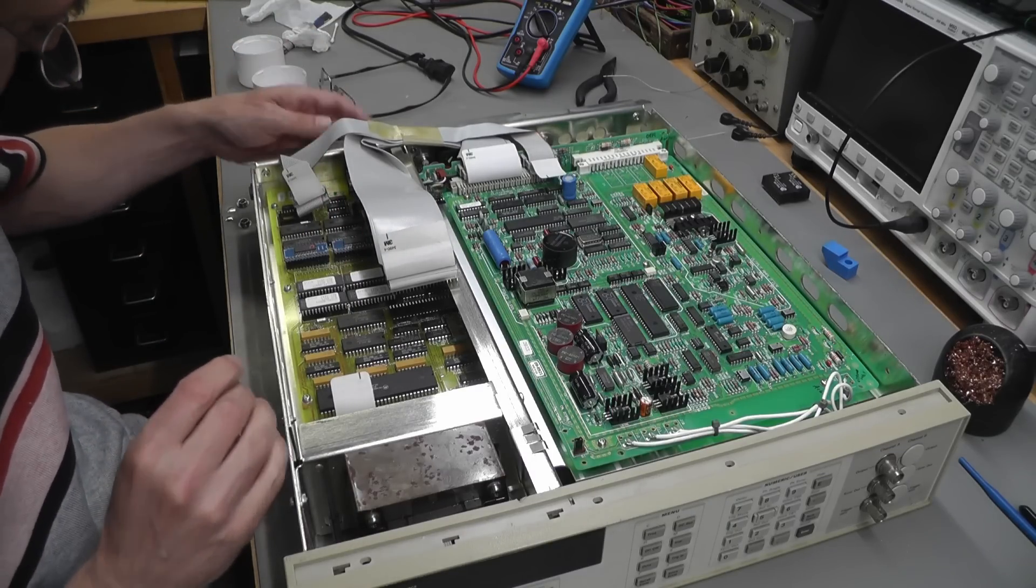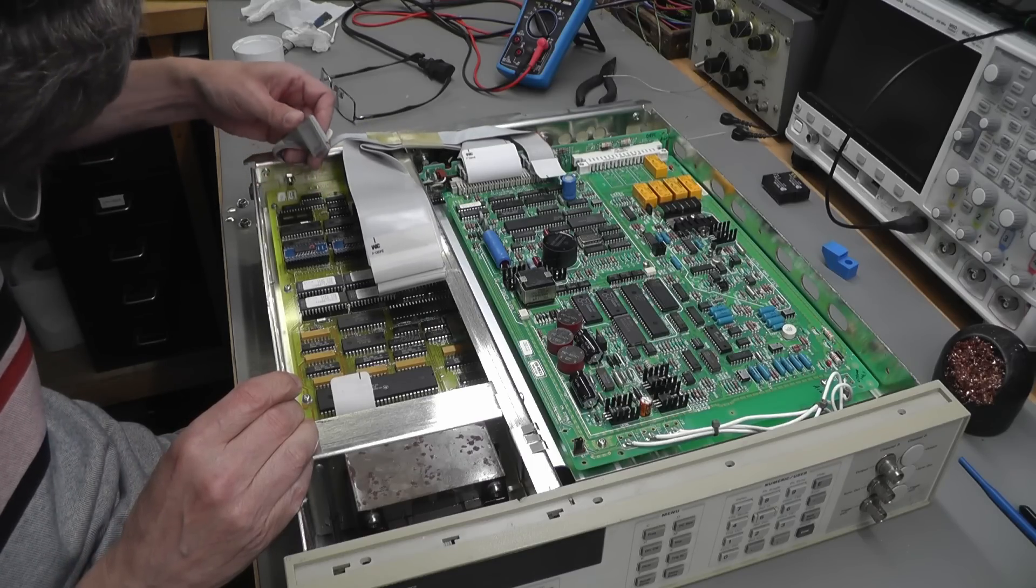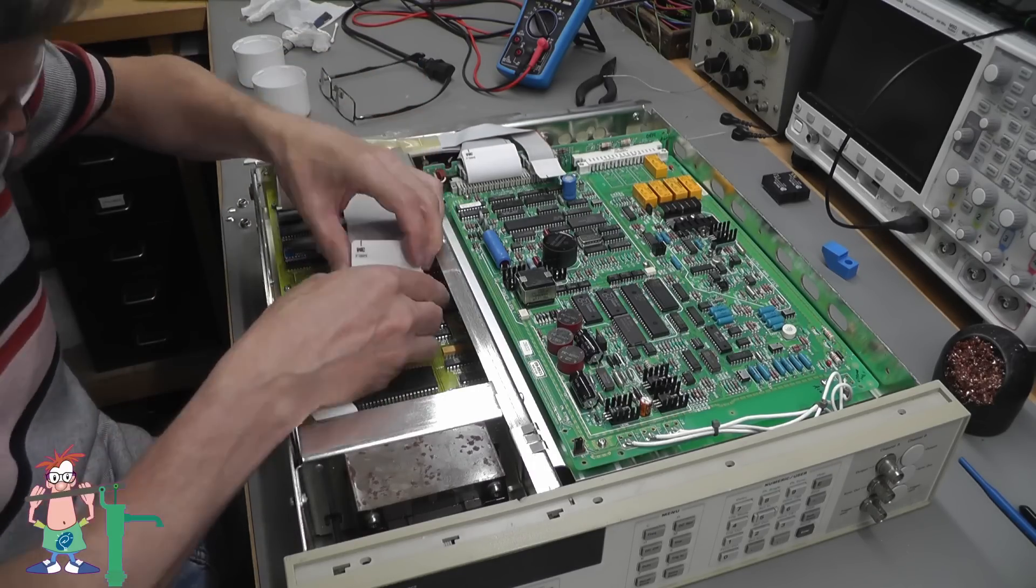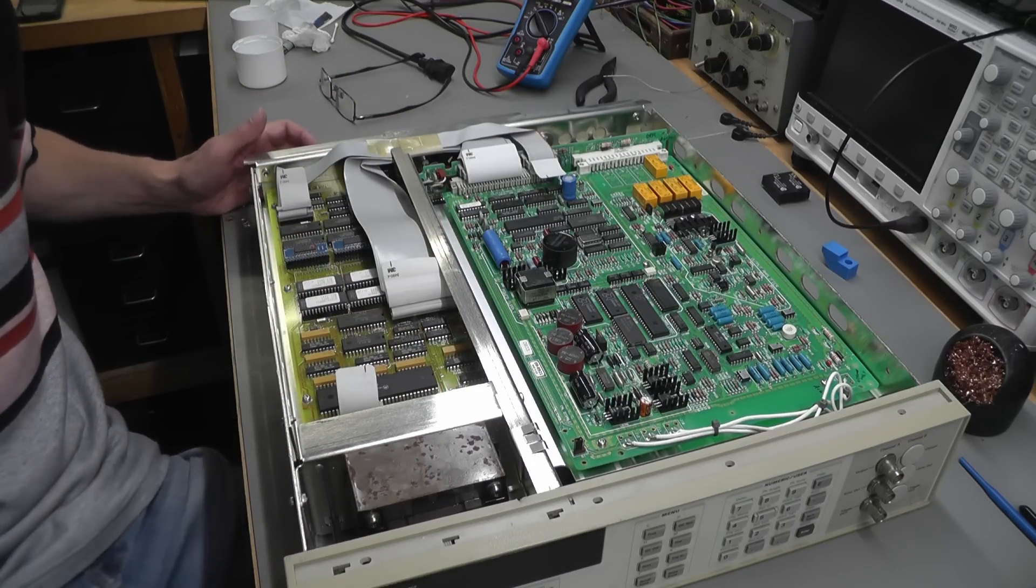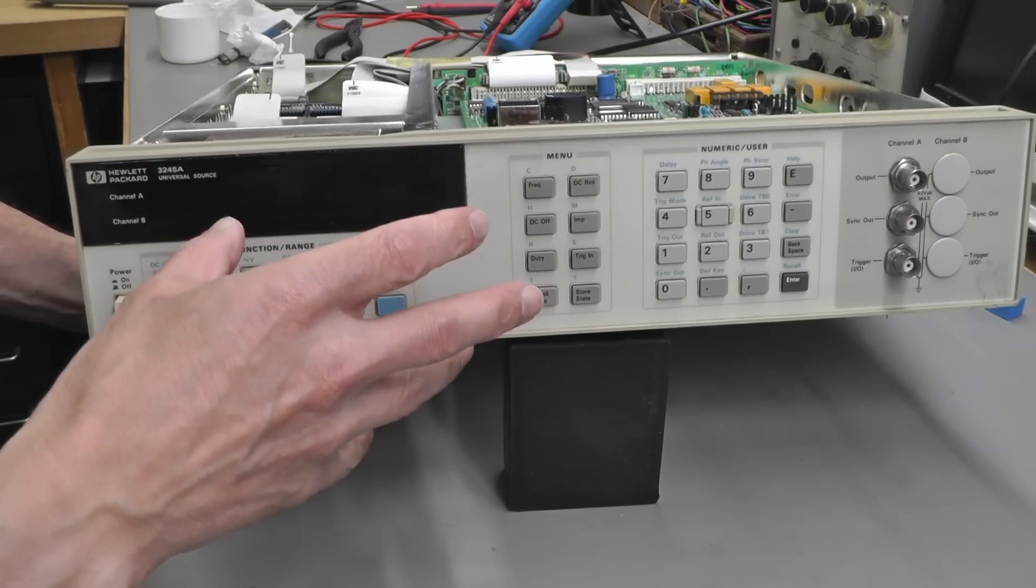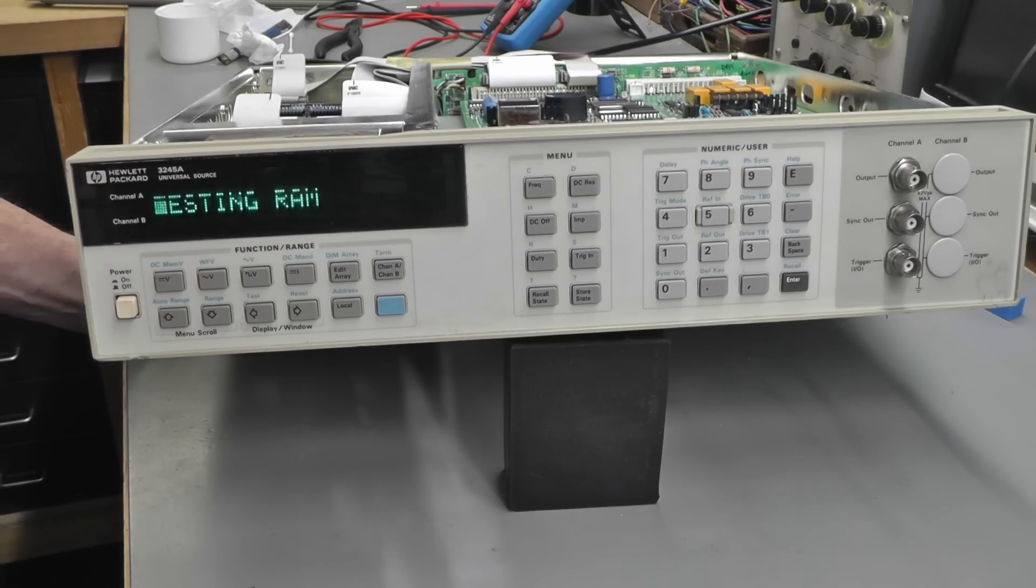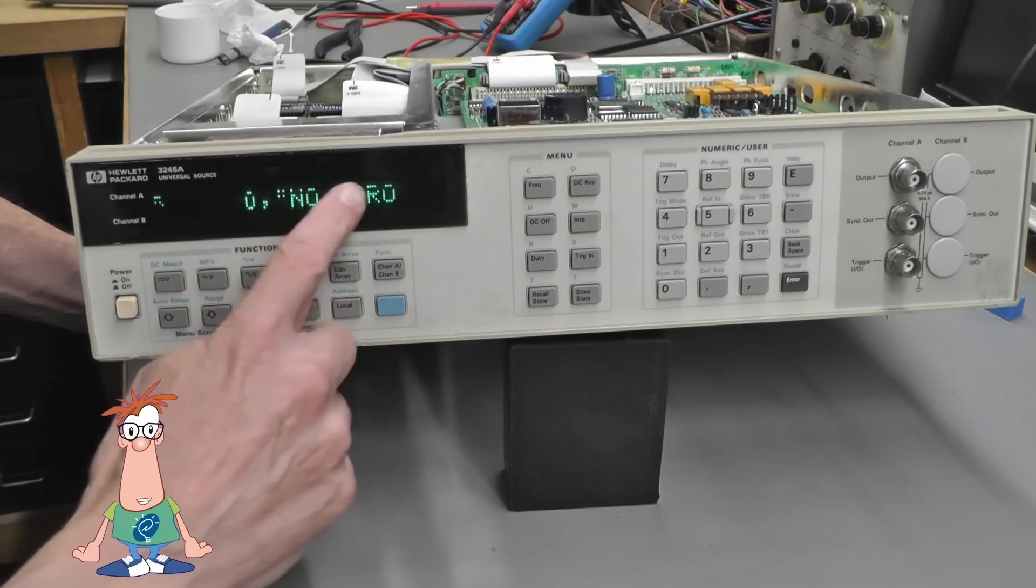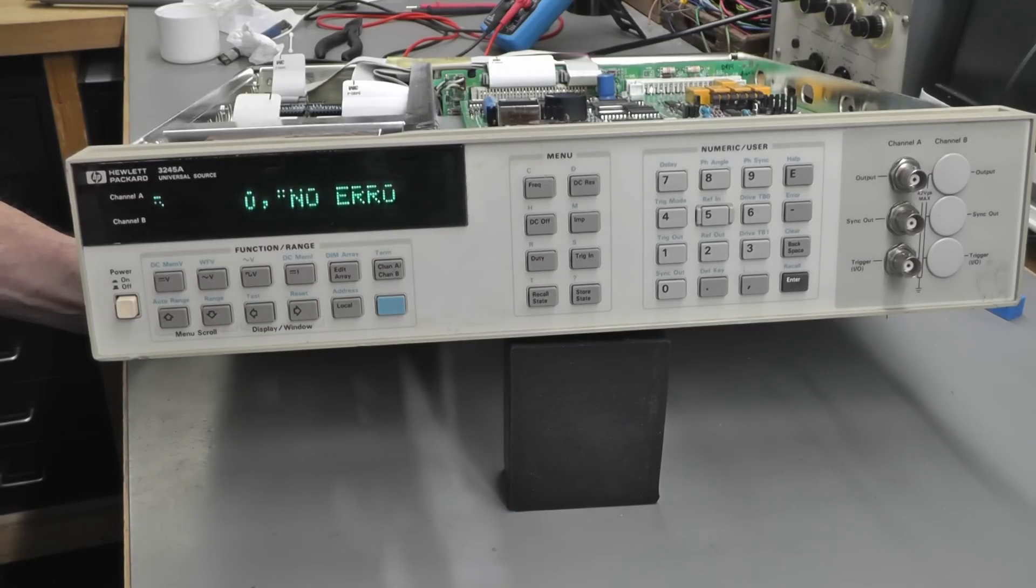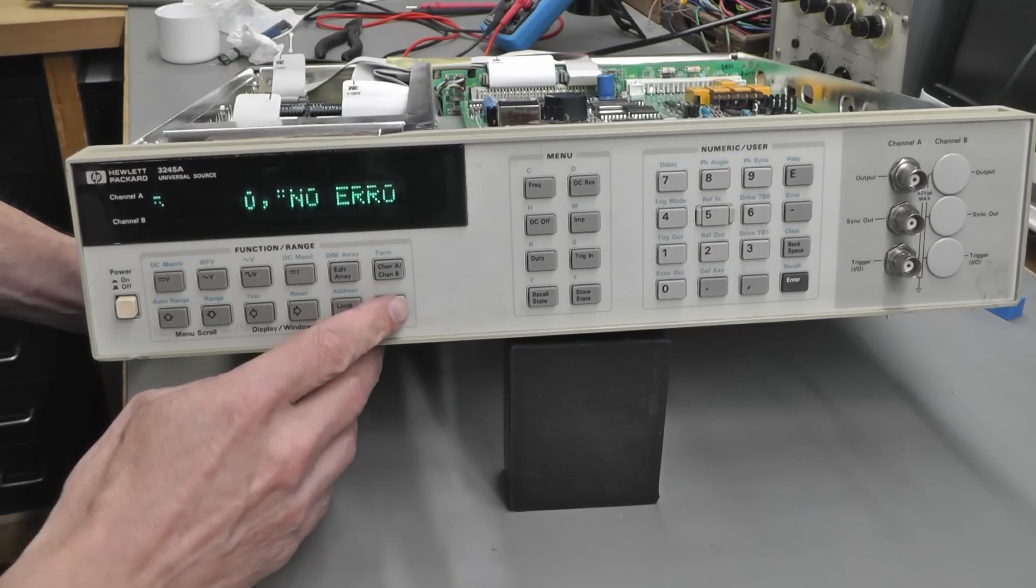Let's fit it back into the chassis and see what happens. I'll not bother with the GPIB connector screws—I need to clean them up. There we go, ready for the power-up. Now I just powered up a second ago and you get the previous errors, so let's power it up a second time. Yes, no errors! Let's take a look—no errors. So looks like we've cleared those two error codes that I got just by changing out the Dallas battery-backed RAMs.